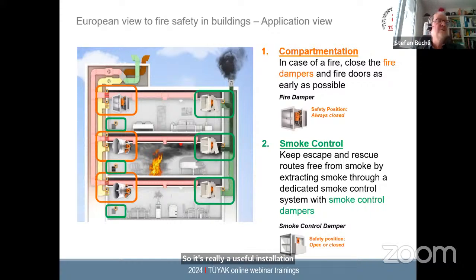Here you can see a little bit of a different philosophy. Point number one to remember is that, as you can see here marked green, it's a separate system from the ventilation system. This is really special and regards the European standards. It's a must to have a separate system. According to European standards, it's not allowed to do smoke extraction via the ventilation system.